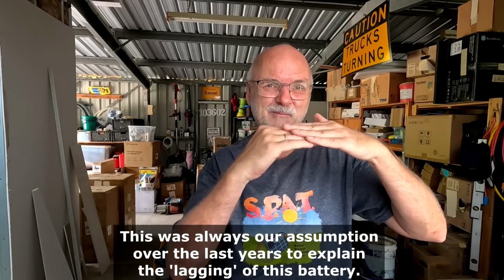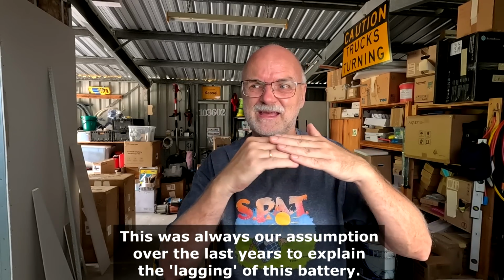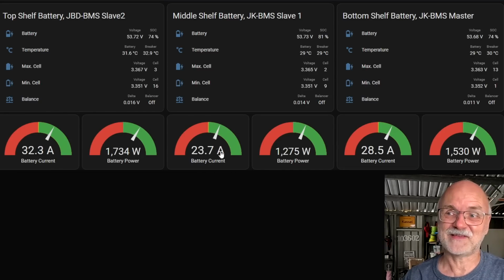And I blame this on the aluminium bus bars, which are sitting on aluminium terminals of the batteries, and there might be some oxidation in between over time, giving an overall higher resistance for this battery, since these batteries are all in parallel connected to this massive 1000 amp bus bar at the back. But it looks like this one has a higher resistance and therefore charges slower.